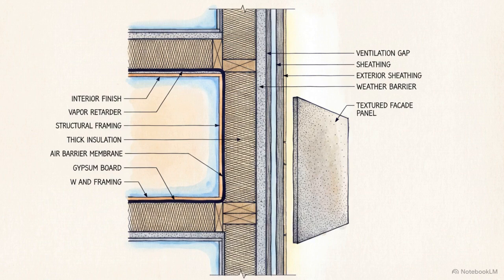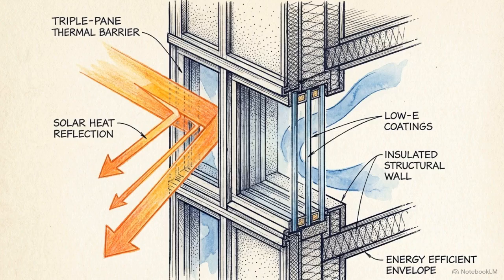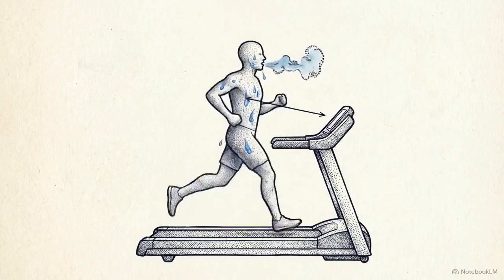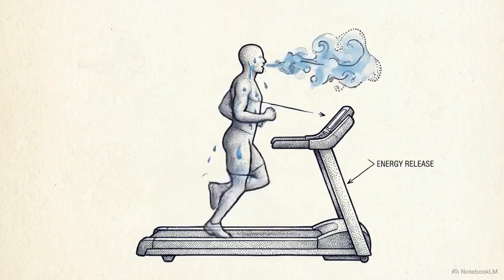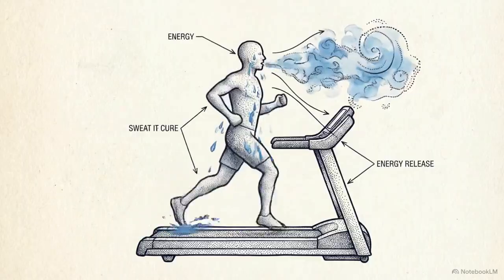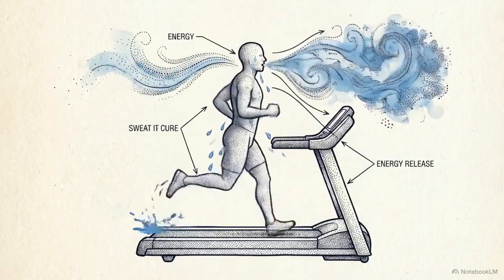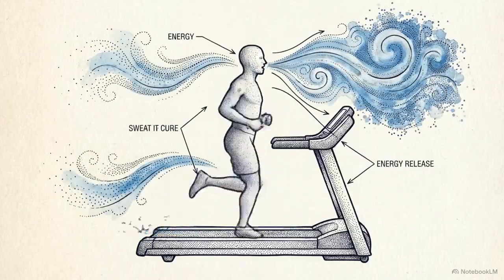An ultra-low energy building envelope relies on extreme insulation and uncompromising airtightness to isolate the interior. It forms a barrier that blocks solar radiation and outside air temperatures, perfectly keeping external sensible heat from entering the structure. But humans operate biologically. Occupants generate a continuous influx of latent heat, specifically moisture from respiration and perspiration.